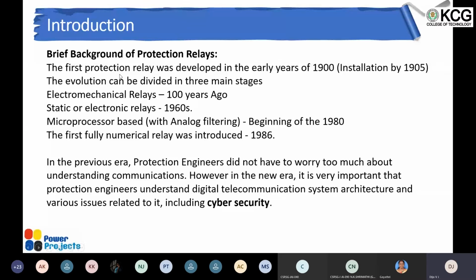That was the original relays, electromechanical relays. Later on, when the electronic industry developed, the static or electronic relays were in use from the 1960s. And later on, the microprocessor-based relays came, in the beginning of the 1980s, with analog filtering, because initially microprocessor relays had some limitations. The microprocessor relay will be measuring the values and calculating. The calculation blocks will be there for comparing with the set value to take a decision on tripping.